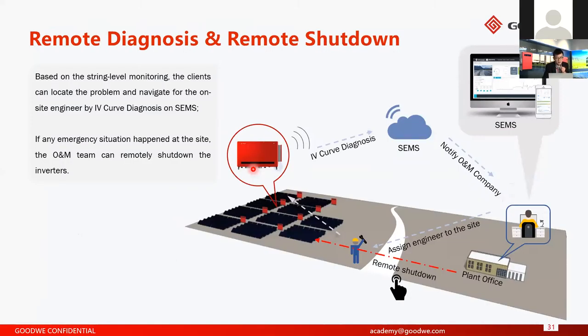And here is remote diagnose and remote shutdown. Actually, we designed the remote shutdown function only for India. You can use an RJ45 cable to connect each inverter hand by hand, and the last one connects to one button. If your PV plant has a problem like a fire, you just need to push the button and the inverters will shut down automatically and immediately. It's very fast, I think less than 200 milliseconds.